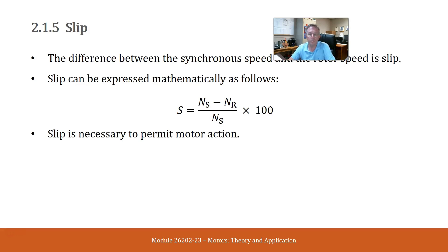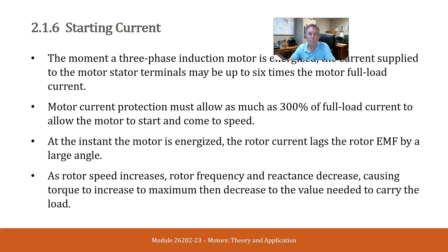Slip can be expressed mathematically with this equation. Slip is necessary to permit motor action. The moment a three-phase induction motor is energized, the current supplied to the motor's stator terminals may be up to six times the motor full load current. Motor current protection must allow as much as 300% of full load current to allow the motor to start and come to speed.